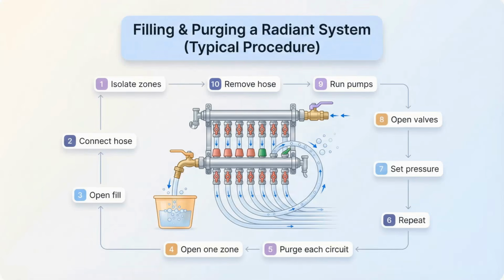System startup begins with filling and venting air. Radiant floors have lots of tubing, so trapped air can be stubborn. A common approach is to isolate all zones, connect a hose to a boiler or manifold hose bib, open the fill, then open one zone at a time, usually starting with the closest. Purge each loop until bubbles stop, then keep going briefly, close it, and repeat. After all zones are purged, set system pressure with the pressure-reducing valve, open zones, run pumps, and let air vents finish the job.